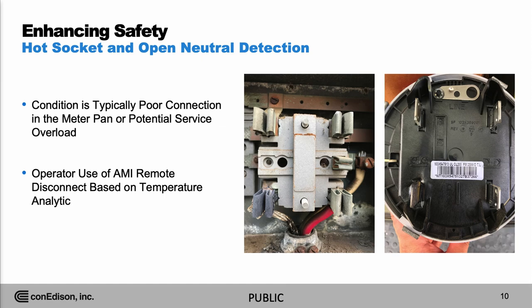Hot socket alarms and open neutral. A hot socket alarm occurs when you have a poor connection in a meter. It could be customer wiring to the meter that's loose, or it could be because the customer is hooking up electric load to the system that it wasn't designed for, such as electric heaters or EV chargers.